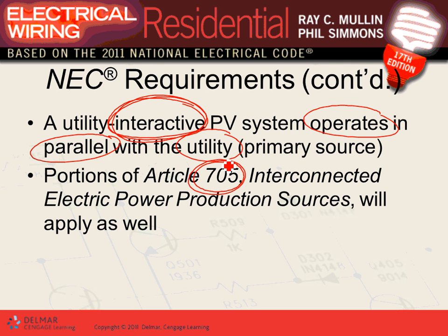Or you can offset your consumption. If you are to do this, you have to have a protection. The protection that qualifies for the solar photovoltaic system, guys, they call it anti-islanding. The anti-islanding system, guys: if the grid is down, the solar photovoltaic system is down. That's it. As simple as this.